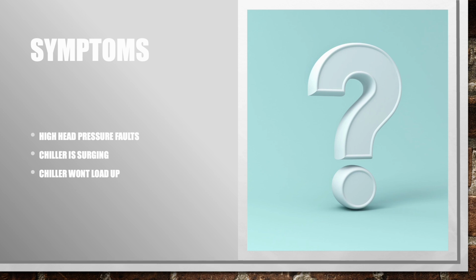Some symptoms of high head pressure on these machines would include, obviously, a high head pressure fault. The chiller could be surging really bad. The chiller may not want to load up due to the condenser pressure limit. You might get that on the screen. Essentially, all that's doing is it takes the high pressure cutout and factors 93% of that, and it keeps the machine unloaded to prevent it from tripping on high head.